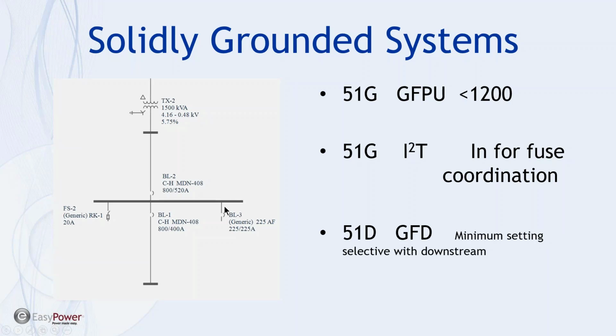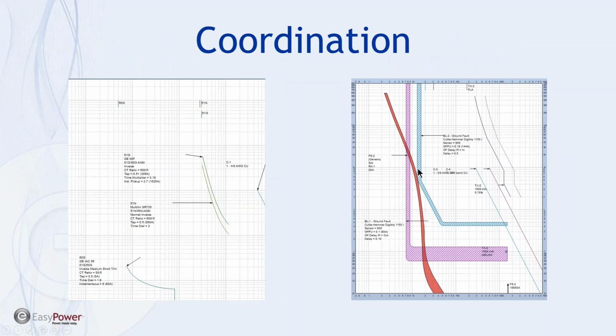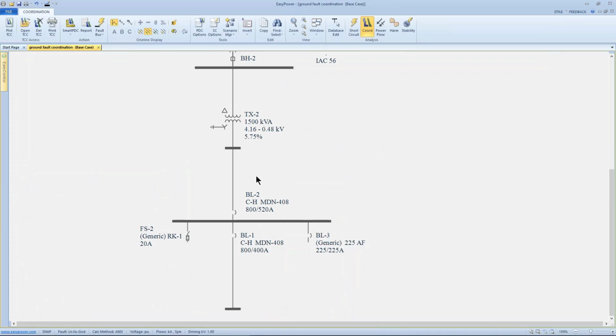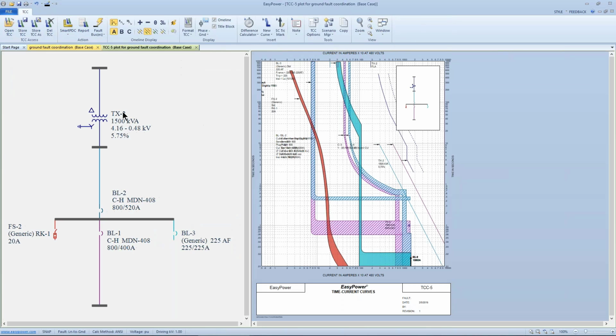So let's see how this looks. The most upstream device we want to set relatively high, and then as we get farther downstream, if we're coordinating with a fuse, we may or may not set the in or out condition of the I²T setting, and then deal with the coordination between the different breakers. So let's see how EasyPower handles this. All right, so in part we're looking at transformer protection and ground coordination. So let's plot all three devices.